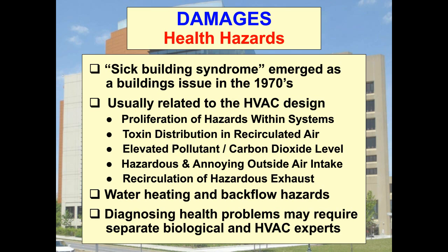Recirculation of building exhaust air can be dangerous. There's a famous research facility where I was called to do an energy study, and in the course of doing that, I discovered that the exhaust from the laboratory fume hoods, where they were dealing with diseases for which there is no known cure, was falling from the roof on warm days. That was because the exhaust was at room temperature, which was cooler than the air outside, so it was denser, and it fell to the ground in the absence of wind. The exhaust was then re-entering the building through a central outside air intake located inside a basement-level truck dock. And as if that wasn't enough, diesel trucks would idle at the truck dock for long periods, injecting diesel exhaust fumes into the building. This would be a lampoon of bad engineering if it weren't real.